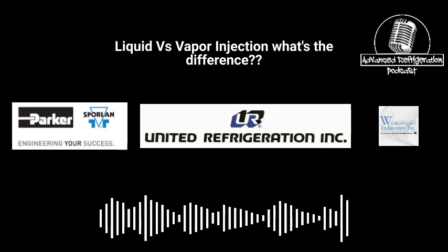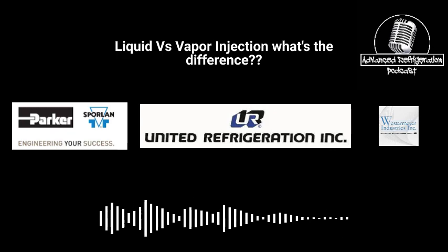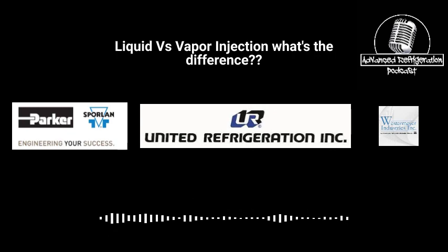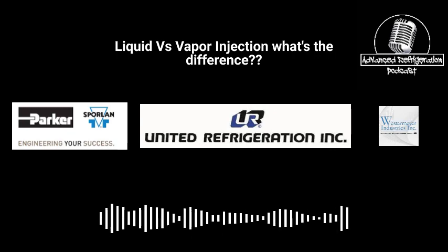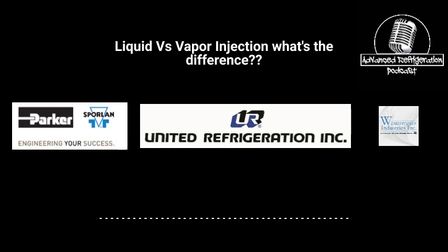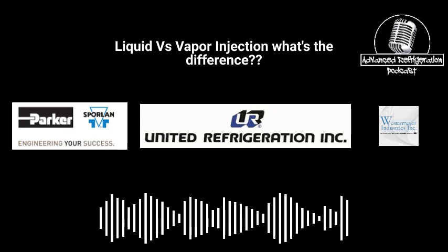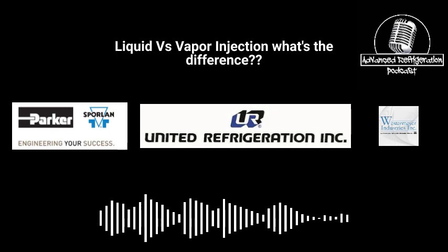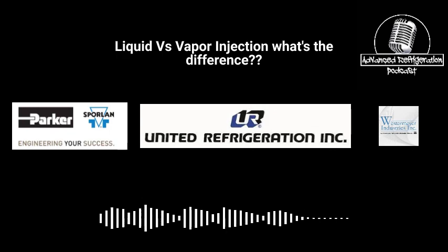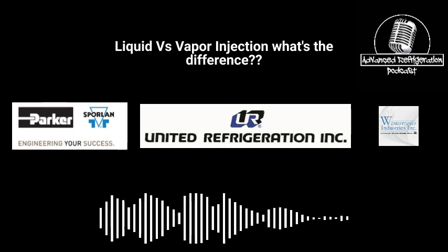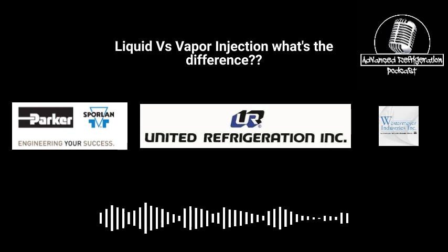We also have the Y1037 valve, which is the liquid injection valve that looks like an expansion valve. Typically it's an F style expansion valve, and it has a bulb on the top, and that bulb is supposed to go on the discharge line. Those are rated for a certain temperature, whether it be 190 degrees, 210 degrees, 230 degrees. And those valves are sized per the compressor.